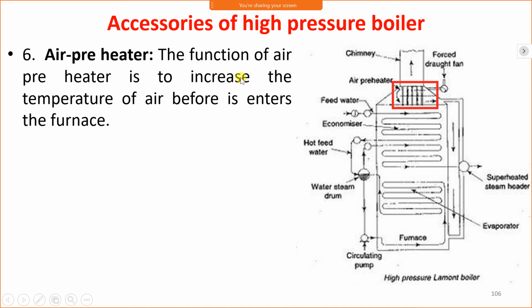The air preheater is used for heating the air which is being supplied to the furnace. This is a furnace, and along with the coal we supply air for proper combustion, because combustion takes place in the presence of oxygen. When we supply atmospheric air directly, its temperature is very low, and it contains moisture also, which can degrade the combustion process. Therefore, we need to supply hot air.